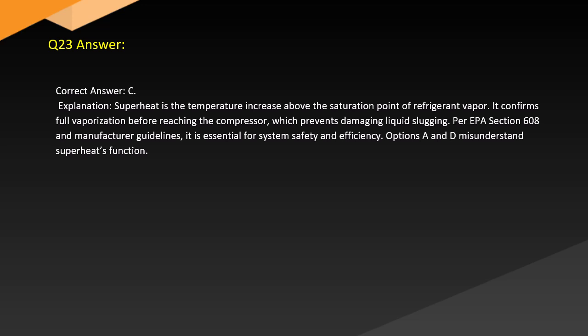Answer. Correct answer: C. Explanation. Superheat is the temperature increase above the saturation point of refrigerant vapor. It confirms full vaporization before reaching the compressor, which prevents damaging liquid slugging. Per EPA Section 608 and manufacturer guidelines, it is essential for system safety and efficiency. Options A, B, and D misunderstand superheat's function.